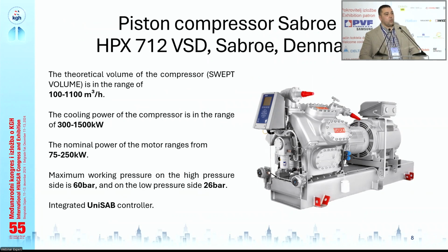For this particular project, we were designing with the HPX 712 VSD. This is a Sabroe compressor, which is designed particularly for heat pump, ammonia high temperature heat pumps, and it's designed based on previous CMO and SMC compressors. Here you can see some details.